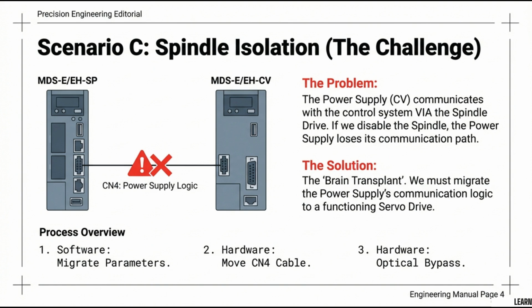Scenario C is spindle isolation. The problem is that the power supply communicates via the spindle drive. Disabling the spindle breaks the communication. The solution is to migrate the power supply's communication logic to a functioning servo drive.